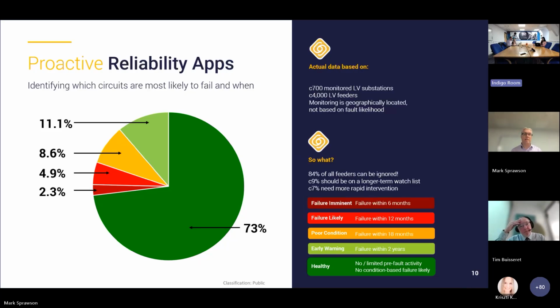So the algorithms are getting quite accurate at being able to say, this is a circuit which you need to intervene on. But that's only half of the problem, because just knowing that circuit is going to fail is not helpful unless you know exactly where on the circuit it is going to fail. So another thing that can be captured through these applications is an impedance value. It gives not just a likelihood of failure, but also the impedance value at which it is going to fail. And that impedance value can be equated into a distance from the substation along the circuit, pinpointing exactly where that location is.